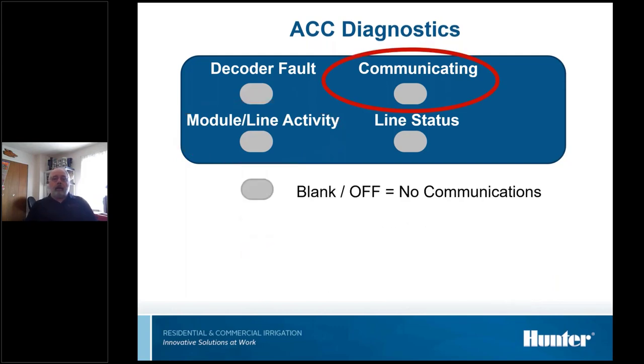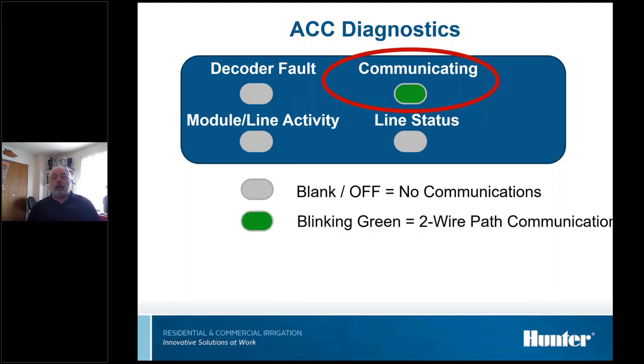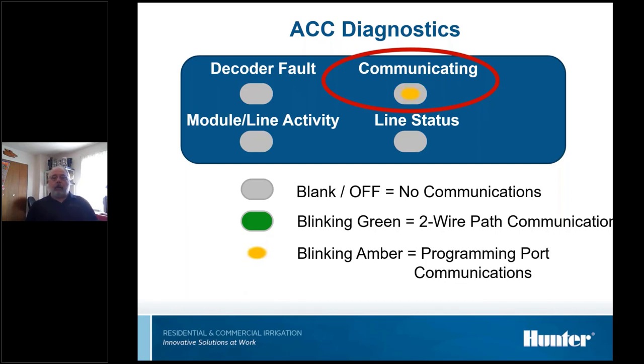The communicating light does a couple things. Normal is blank. When it sends the signal down the two-wire path, and this is very, very quick, it blinks green, but unless you're staring right at it, you won't even notice it. It's so quick. And it blinks amber or yellow when we're programming decoders through the module.